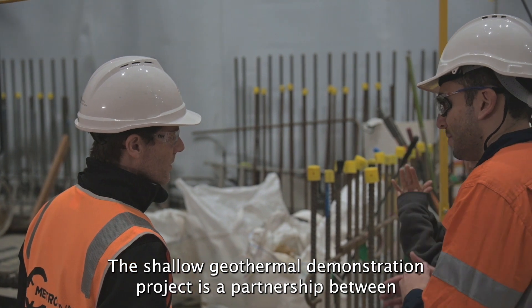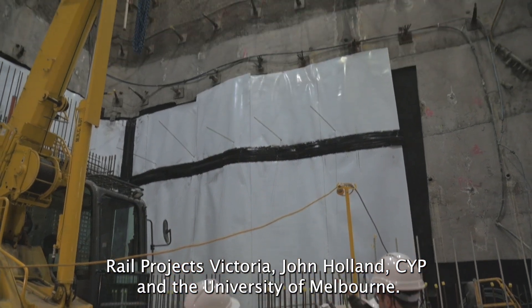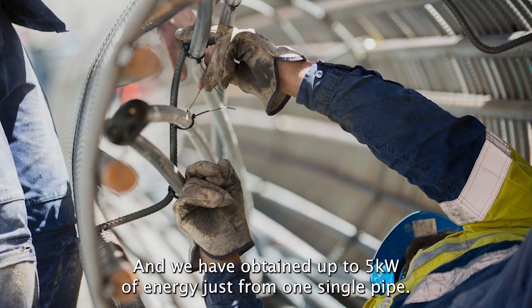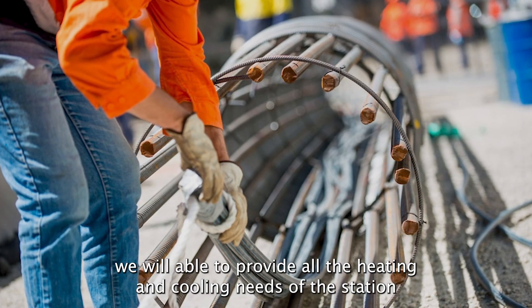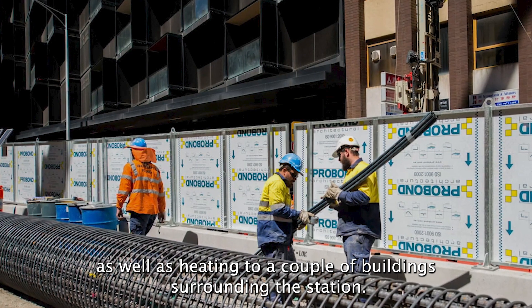The shallow geothermal demonstration project is a partnership between Rail Projects Victoria, John Holland, CYP, and the University of Melbourne. We have obtained up to five kilowatts of energy from just one single pipe. If we were to activate all 69 pipes of just one shaft, we will be able to provide all the heating and cooling needs of the station as well as heating to a couple of surrounding buildings.